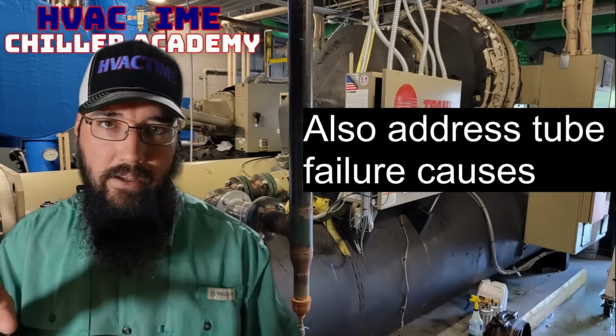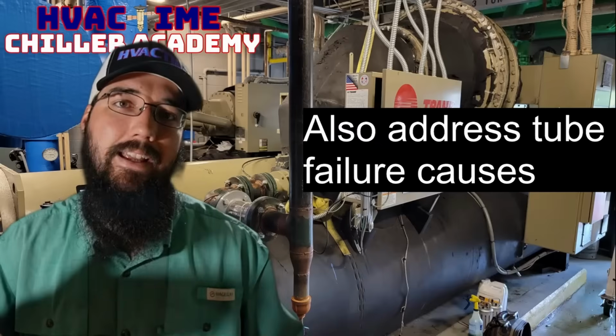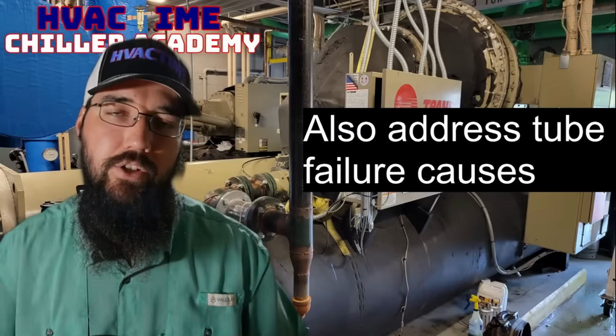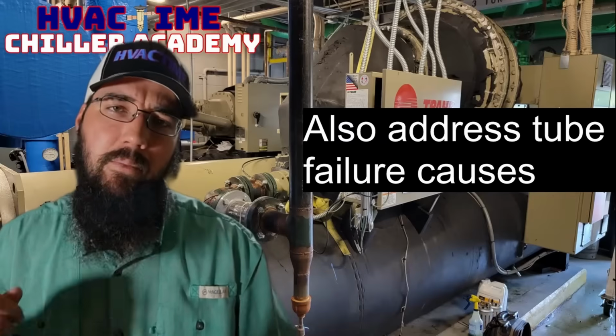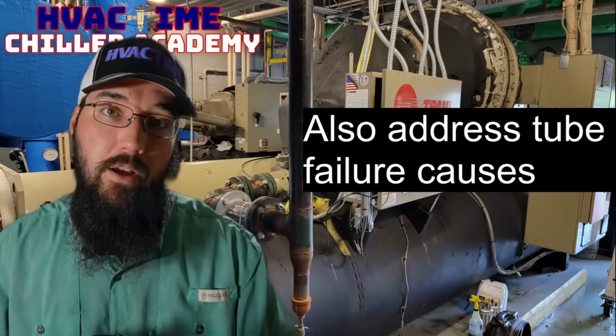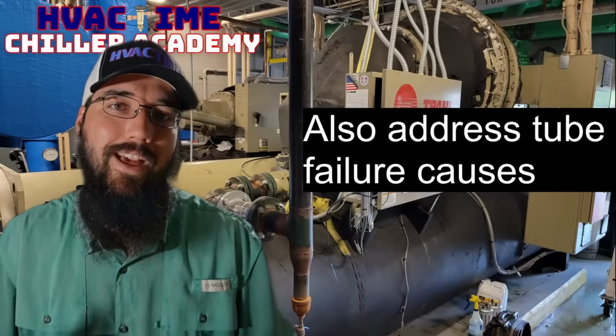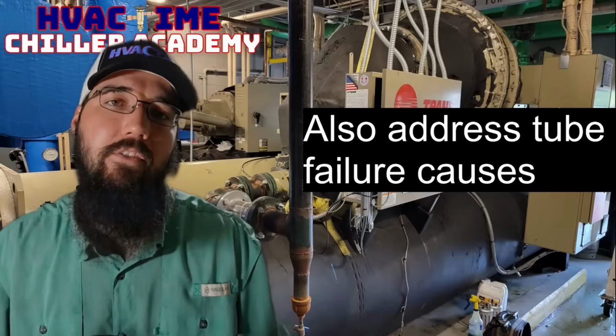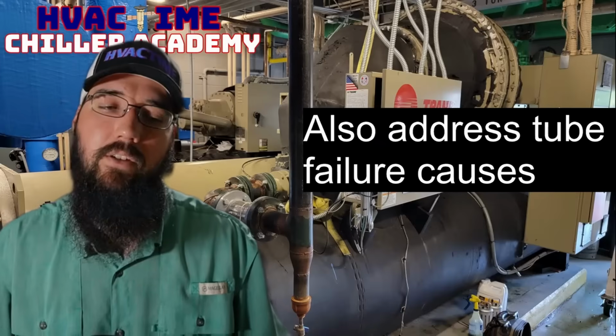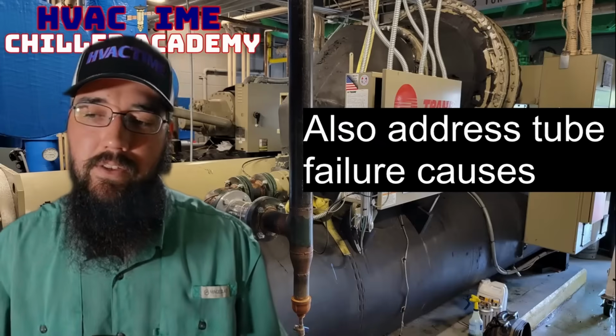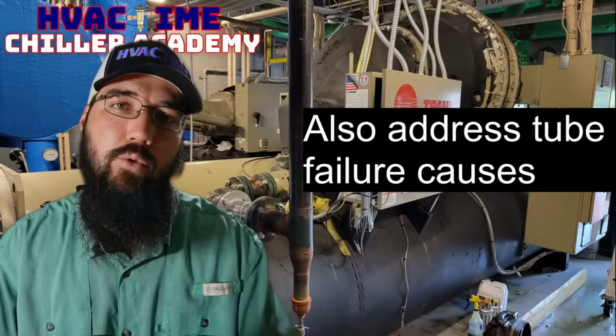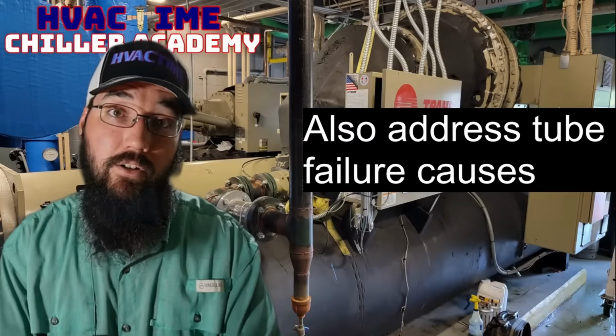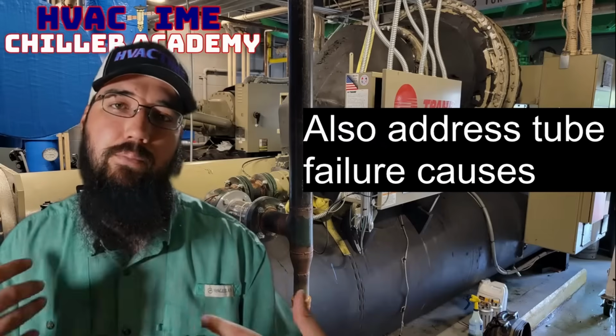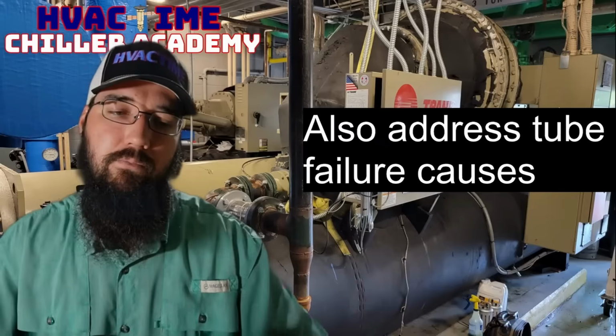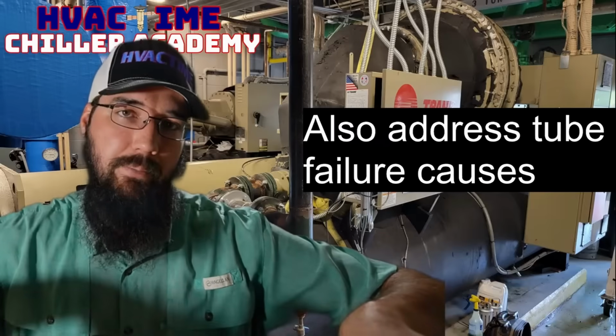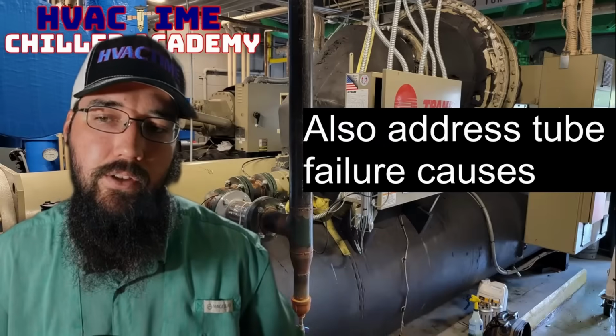And if you had a tube sheet leak where it was leaking at where it's swedged into the end plate, a lot of the time I've found that putting the plug in the first place is actually enough that it will inevitably seal. Not always, but I found that is a common way to get one to reseal without having to literally re-swedge it. Just putting a plug in forces that swedge to expand out and reseat into the tube sheet itself.